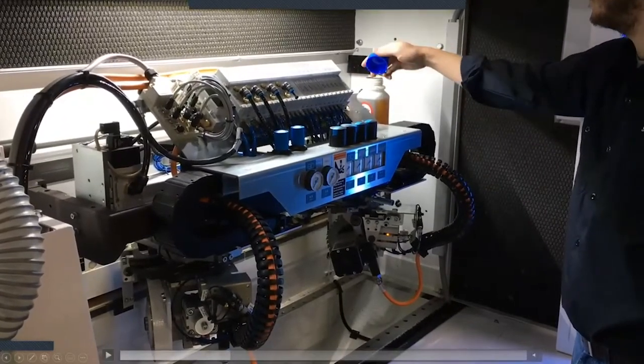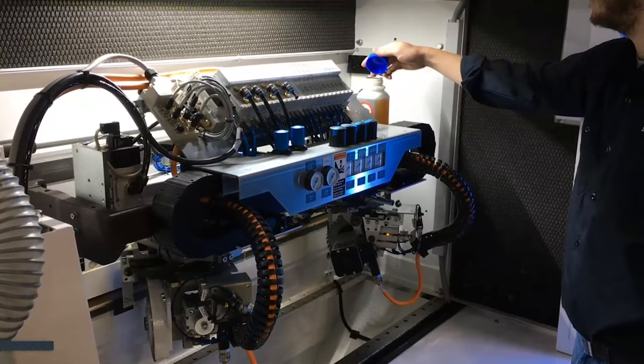This particular unit, the PK25, does have an automatic oiler system on it, located on the top right. This oiler, if it runs out, will throw an alarm. So remember, if you do see an end trim alarm, this oiler area would be the first place I look. And if it's full, then I would look at the prox switch behind it. Just process of elimination.